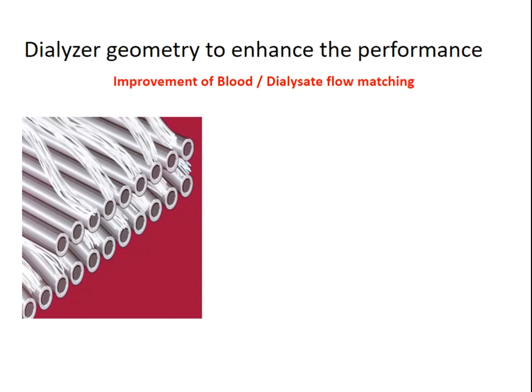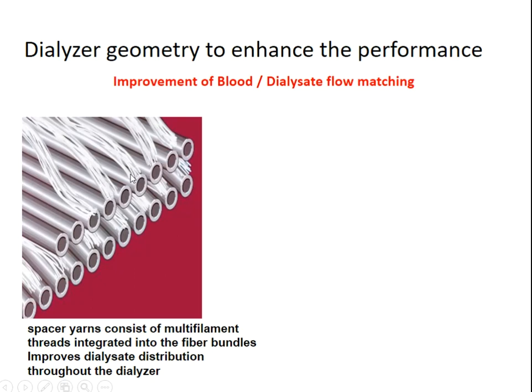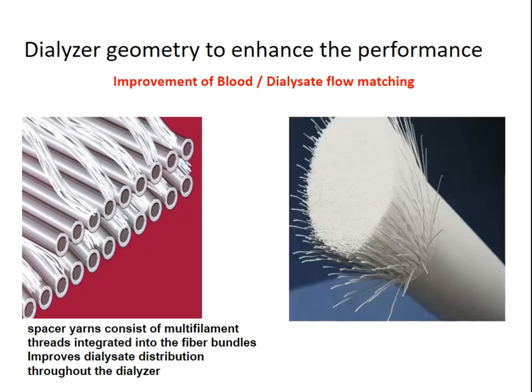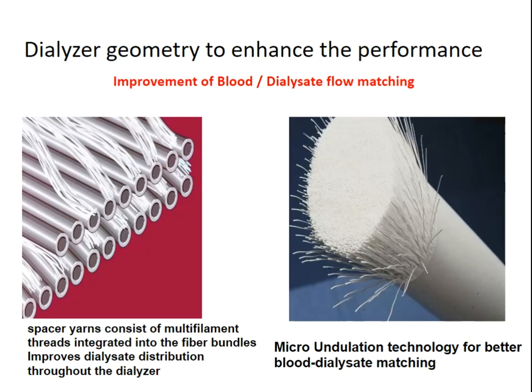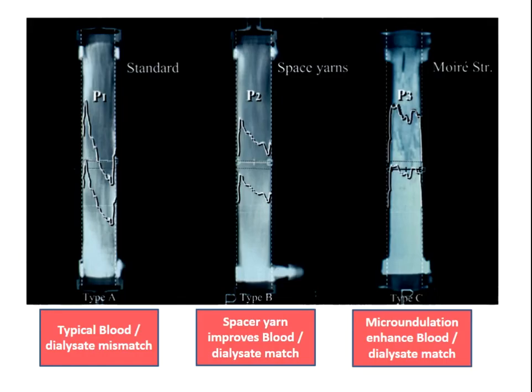Two technologies can improve dialyzer performance through better flow matching. First, spacer yarns between fibers separate adjacent fibers from each other — multi-filament threads integrated into the fiber bundles that improve dialysate distribution throughout the dialyzer. Second, microundulation technology uses non-straight, microundulated fibers for better blood and dialysate matching. Three graphs demonstrate the typical blood-dialysate mismatch, with improvement from spacer yarns and much greater improvement with microundulation technology.